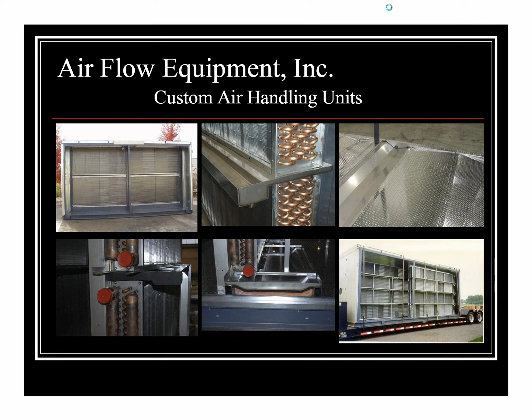Just talking a little bit about heating coils, IFBs. One of the things we've all seen and I'm sure lived with is mixing cold outside air and warmer return air during the heating season. We will definitely use integral face and bypass coils, which are fairly standard: steam coils with face and bypass dampers configured around them. That's something up front that, if we're doing a project together, we can work out. First, make sure we've sized the heating coil properly, that we're providing the true heating load so that we're not going to tend to overheat.